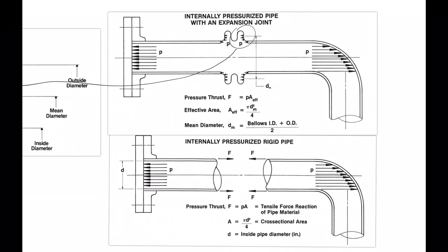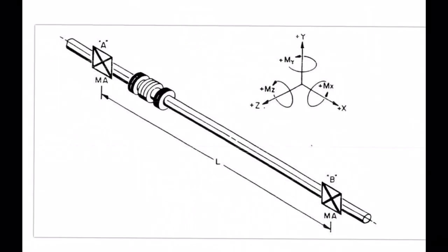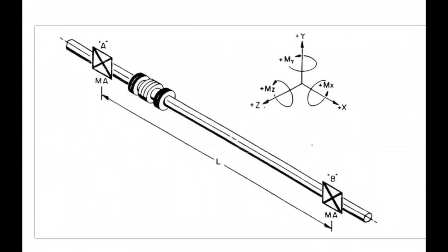In a nutshell, unrestrained expansion joints must be used in anchored and guided systems which require the anchors at each end of a pipe so that the pressure thrust will be reacted at the anchor points. Here I have shown a very simple piping system where there is one expansion joint and two anchors. Let's say this pipeline is supposed to be working at a very high temperature, so this bellow is introduced to accommodate certain thermal growth. Then what will be the load acting on the main anchors?